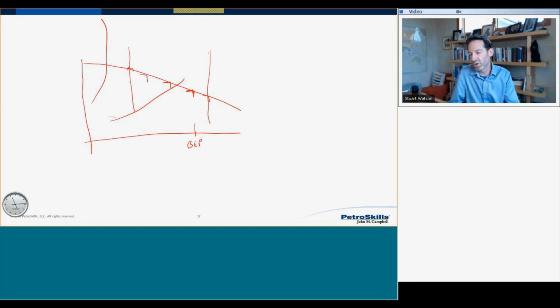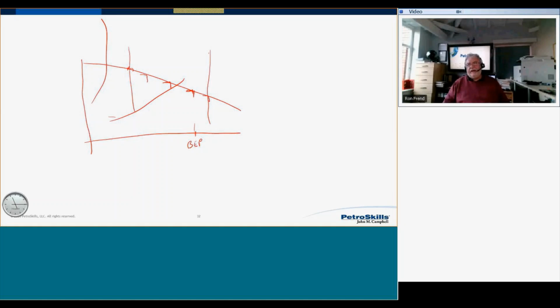So typically what I would do there is start talking to pump vendors, and talk to other operators in the area, people that are running this pump already, discovering what they're finding in this application and what's working well for them. Then I use that data to help with my material selection for the new pump that I'm specifying. I'm not sure if that helps, but from a design perspective that's a very difficult question to answer, and I don't know if I've answered your question. I think I would also get into a narrative with a vendor and say, look, this is what I'll accept. If your pump is doing this with this process fluid, how bad is it going to get? And they should have that information.